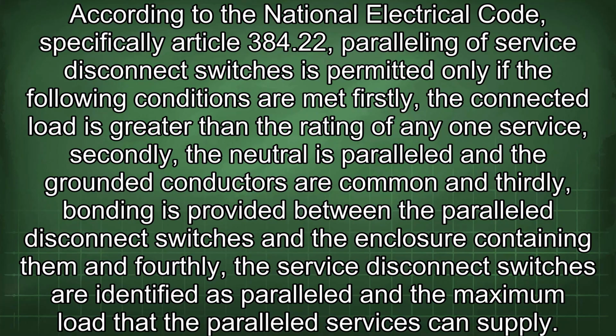According to the National Electrical Code, specifically Article 384.22, paralleling of service disconnect switches is permitted only if the following conditions are met. Firstly, the connected load is greater than the rating of any one service. Secondly, the neutral is paralleled and the grounded conductors are common. And thirdly, bonding is provided between the parallel disconnect switches and the enclosure containing them. And fourthly, the service disconnect switches are identified as paralleled and the maximum load that the paralleled services can supply.